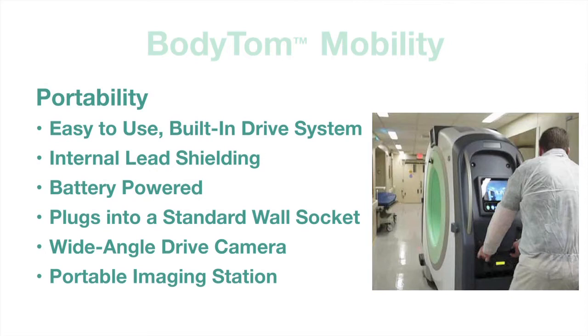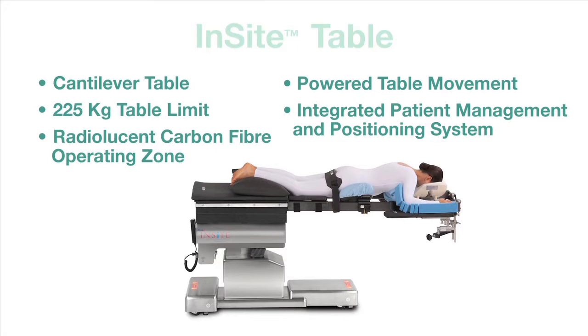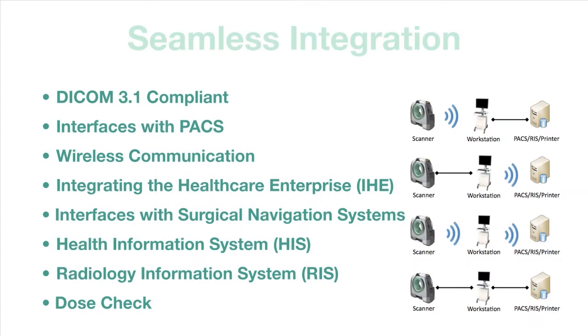The mobile gantry is battery-powered and driven by internal motorised wheels for general transport. Retractable caterpillar tracks are lowered for scanning. It plugs into a standard wall socket to allow for charging. The BodyTom can stay on standby for up to 14 hours or around 4 to 6 hours of scanning time without needing to be charged.